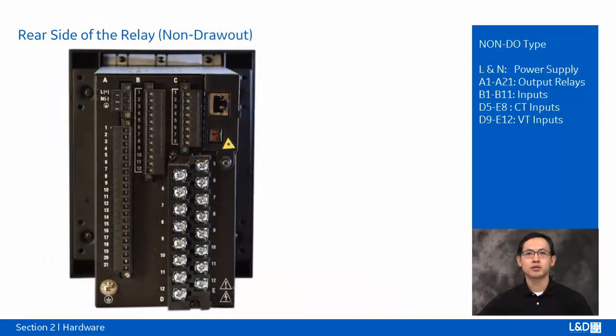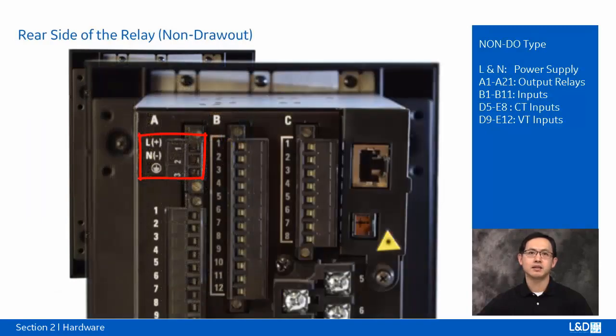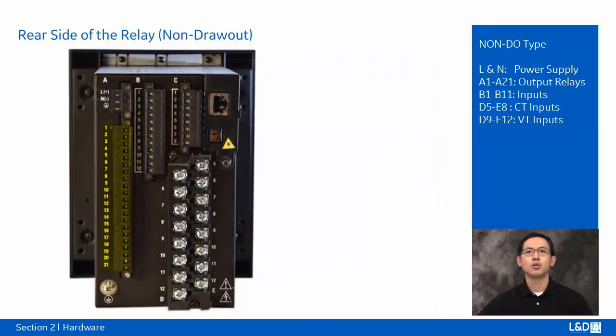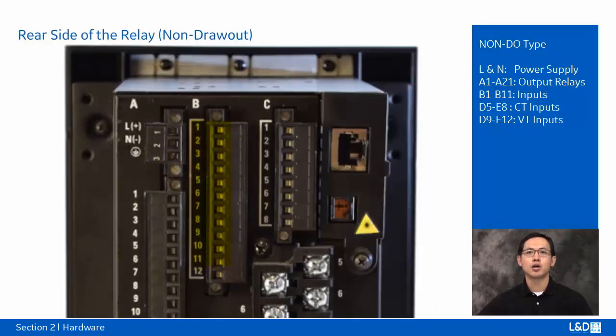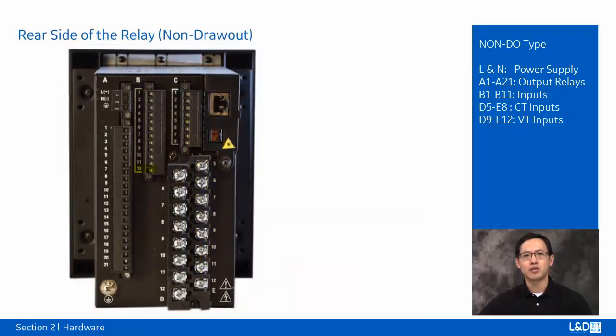In the non-drawout type relay, the terminals L and N are used for the AC and DC power supply. A ground port is also provided in the same connector. The whole column A1 to A21 is used for the output relays. Column B1 to B11 are for inputs. B12 is for chassis ground. In columns D and E, the CT-VT inputs are the same as the drawout type relay.